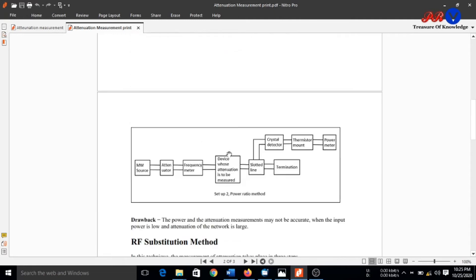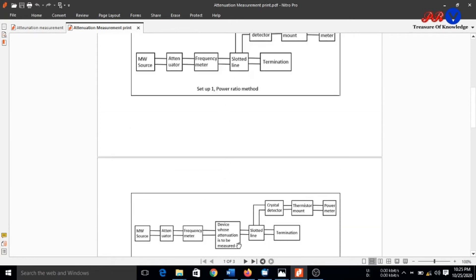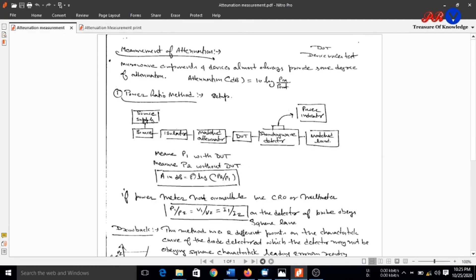In step 2, we will use our device under test whose attenuation is to be measured. We will connect the device whose attenuation is to be measured. In the diagram, attenuation in dB is given by 10 log(P2 / P1). P1 is the output power indicated by the power meter when the device under test is connected in the bench, and P2 is the power in the power meter without the device under test connected.